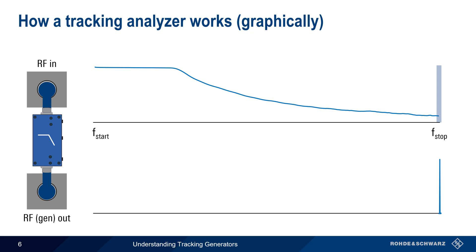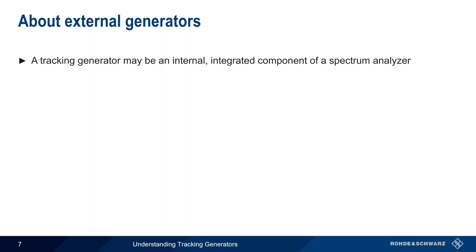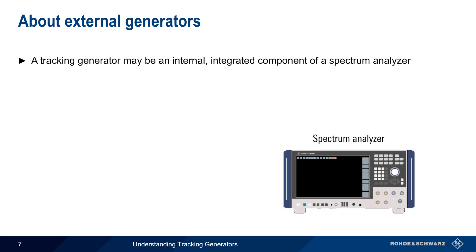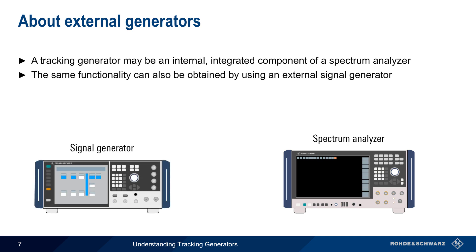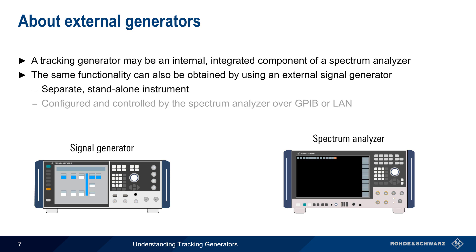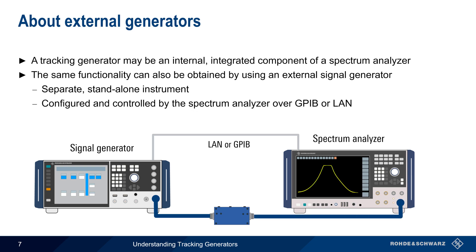Network measurements made using a tracking generator are often sufficient for many basic RF applications. Tracking generators may be an internal, integrated component of a spectrum analyzer, but this functionality can also be obtained using an external signal generator as a source. This separate, standalone instrument is controlled and configured by the spectrum analyzer, typically over a GPIB or LAN connection. This allows synchronization of the generator output and analyzer measurement sweep, enabling the same types of measurements as those made with an internal, integrated tracking generator.